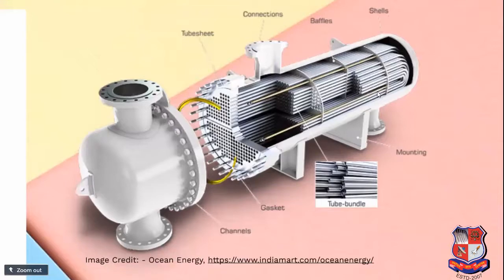Basically, the heat exchanger you are observing is a U-tube type of heat exchanger. The support over here is a saddle support, and again the same nozzles are provided for the shell side, and the shell is enclosing the tubes along with the shell side fluid. You can clearly see the fluid entering from the upper side of the tube sheet and coming out from the bottom side of the tube sheet, because here the pass partition is given. Okay, and while connecting the head with the shell, there is a gasket in between them. This yellow color is the gasket, and this bunch of tubes is the tube bundle.